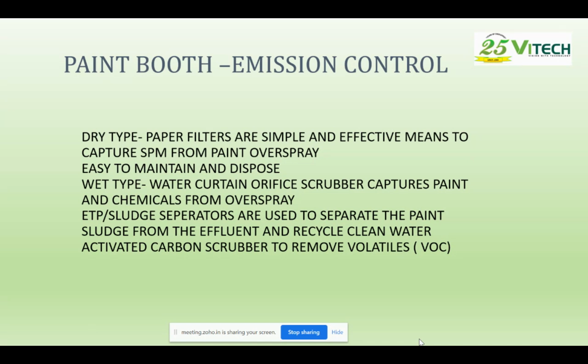The paint consists of not only solid particles, but also a certain amount, 30 to 40% or 50%, of chemicals. These are called volatile organic compounds, which can also get released into the atmosphere. From the paint booth, the blower exhausts all of it; only the suspended particles are captured in the filters, and the VOC component can escape from the booth. In such a case, we need to provide another mechanism to eliminate these volatile compounds.